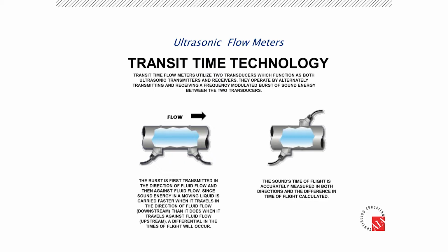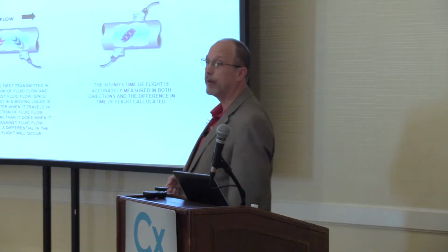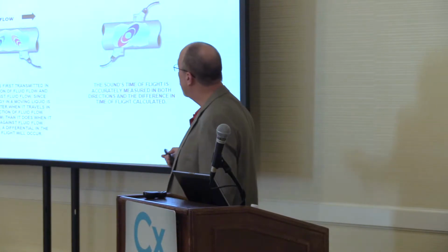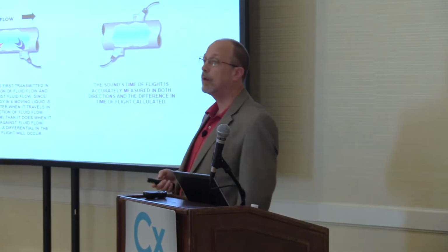we basically have two different technologies. Here's the most common one for explaining the application. We've got a pipe. Flow is going from left to right, and we have two sensors. We send a sound burst from this sensor downstream to this sensor, and we measure how long it took. We measure the time: transit time flow meters. Then we send a sound burst from here back to the other side of the pipe. Because it's going against the flow, it takes a longer period of time.